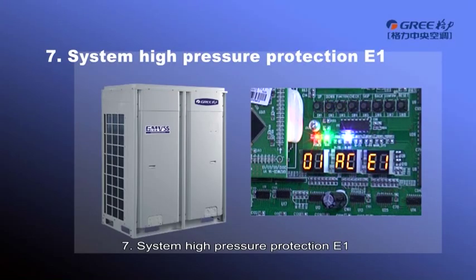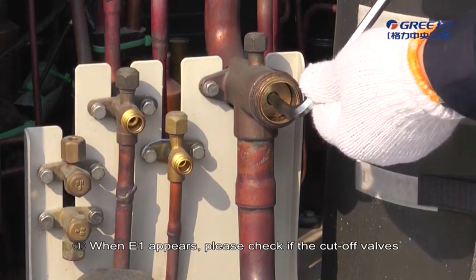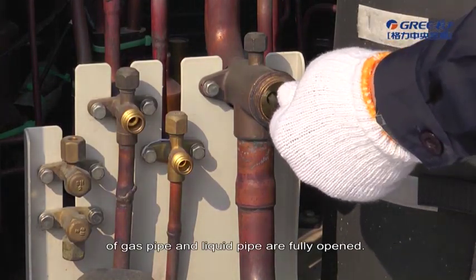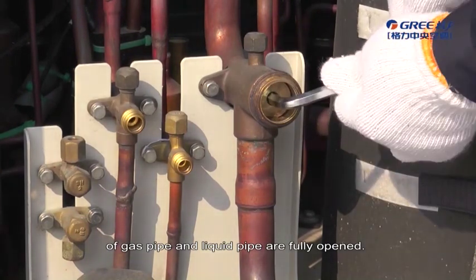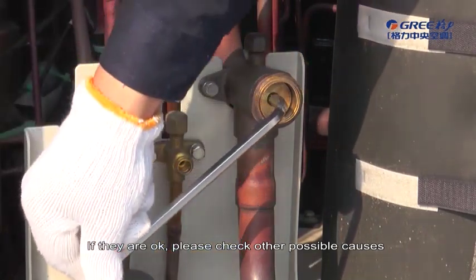System High Pressure Protection E1. When E1 appears, please check if the cut-off valves of gas pipe and liquid pipe are fully opened. If they are OK, please check other possible causes.